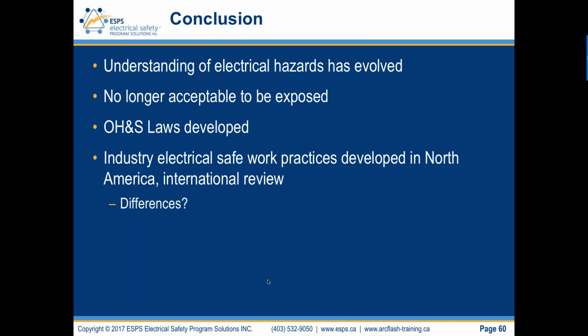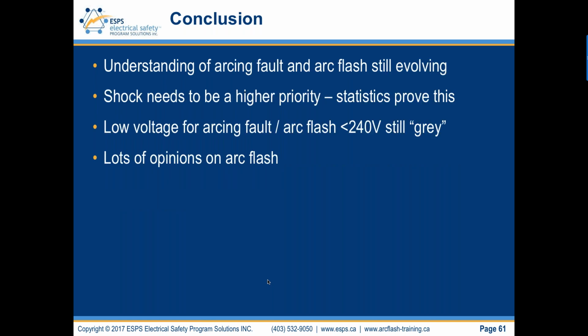So one of the key messages today is, yeah, we need to get it right. But all of this has saved workers' lives. It has reduced the risk of exposure. And when energized electrical work is performed, the residual risk level has been reduced. But again, the holes, the gaps, the problems I've identified will change that residual risk level to not being what we believe it should be if the controls are properly being applied.